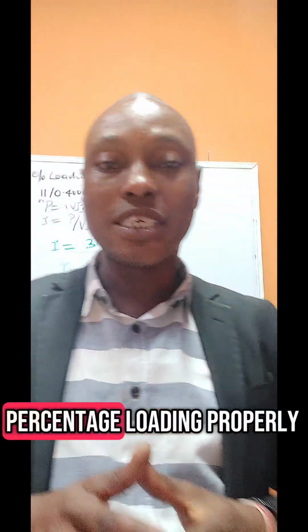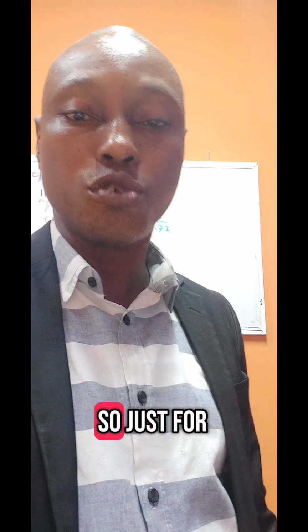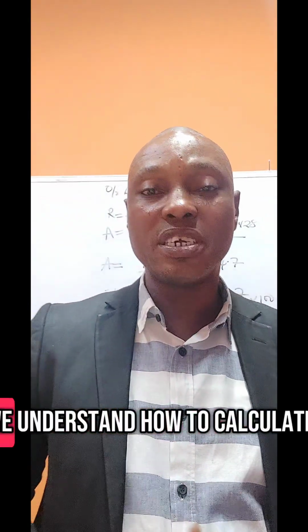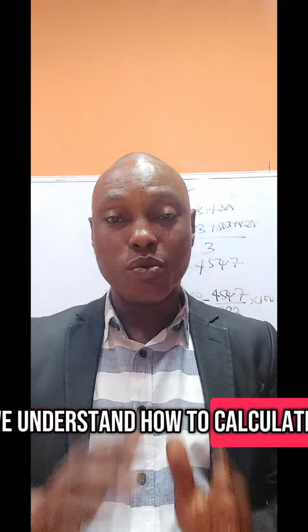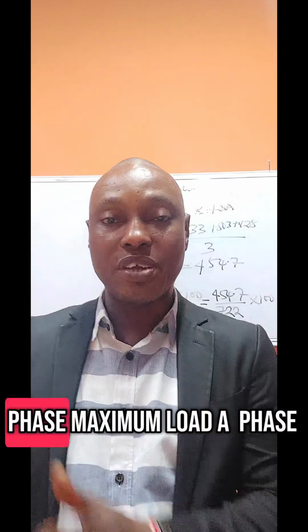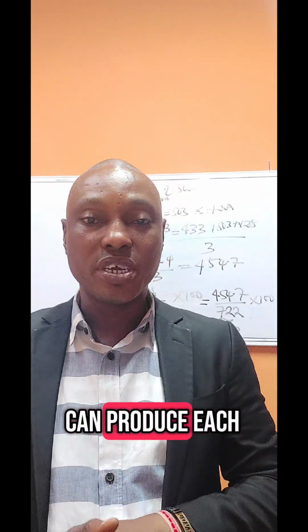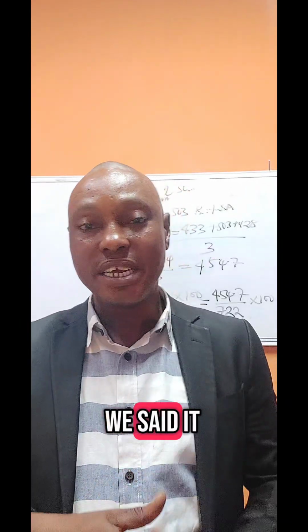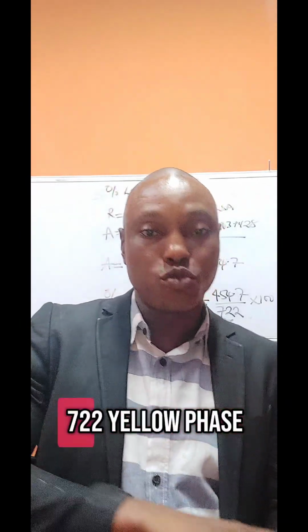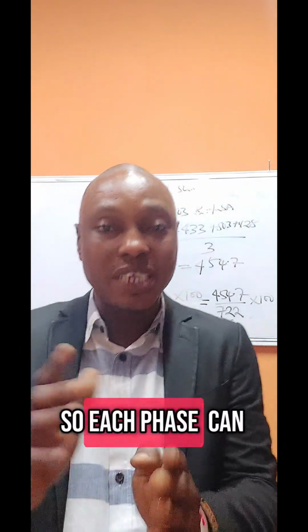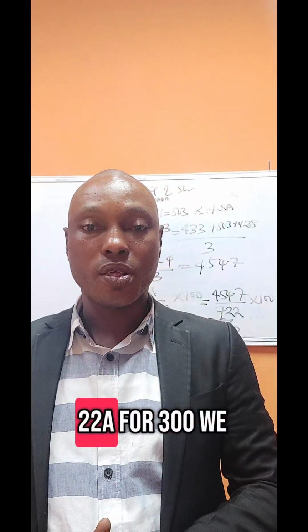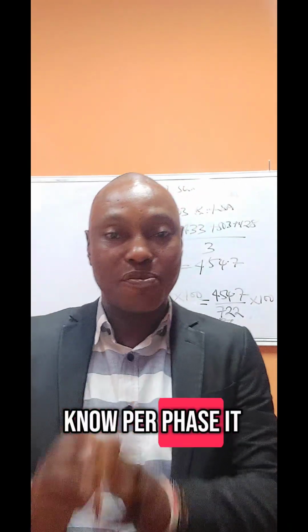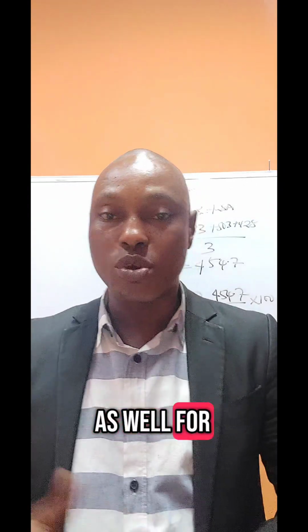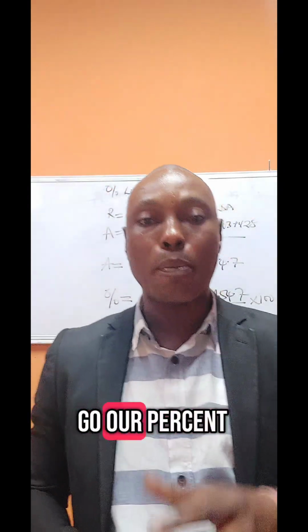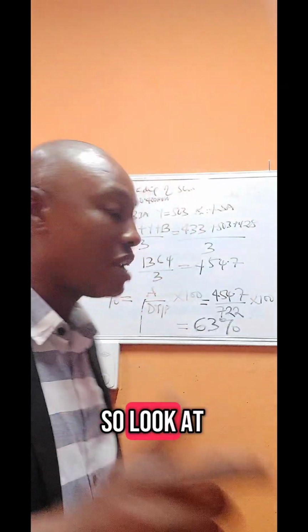We're now going to our percentage loading properly, of a transformer. So just follow. Since we understand how to calculate the maximum load a phase can produce in a transformer, for 500 kVA we said it is 722 amps per phase: red phase 722, yellow phase 722. So each phase can give us 722. For 300, we know each phase can give us 433 amps. You can calculate as well for 200 kVA or 50 kVA. So since you know now, we'll go to our percentage loading properly. Look at the formula I wrote.